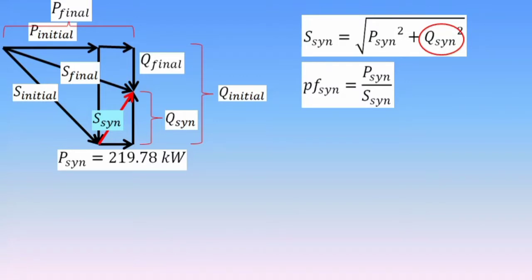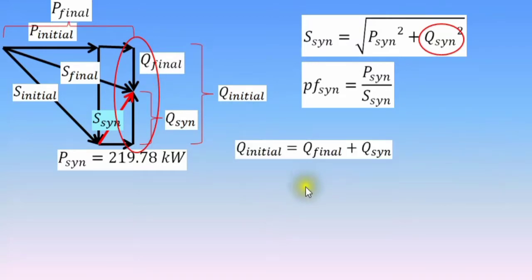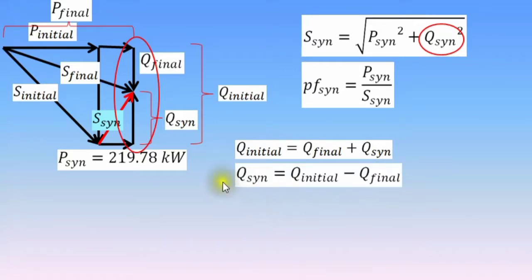Again, let's analyze this phasor diagram. One way of solving for its reactive power is by taking a look at this part of this phasor diagram. It could be analyzed that the initial reactive power equals the final reactive power plus the reactive power of the synchronous motor. To determine the reactive power of the synchronous motor, transpose the final value of the reactive power to the other side of the equation. We have the reactive power of the synchronous motor equals initial reactive power minus final reactive power. So let's determine these values.